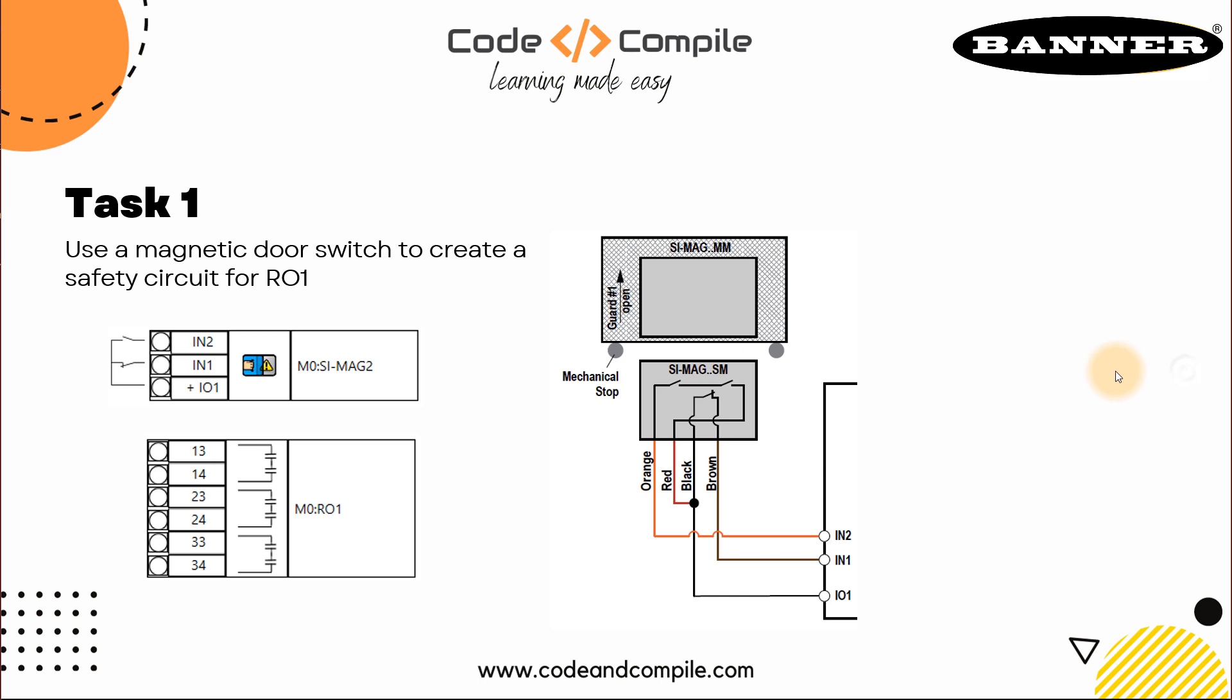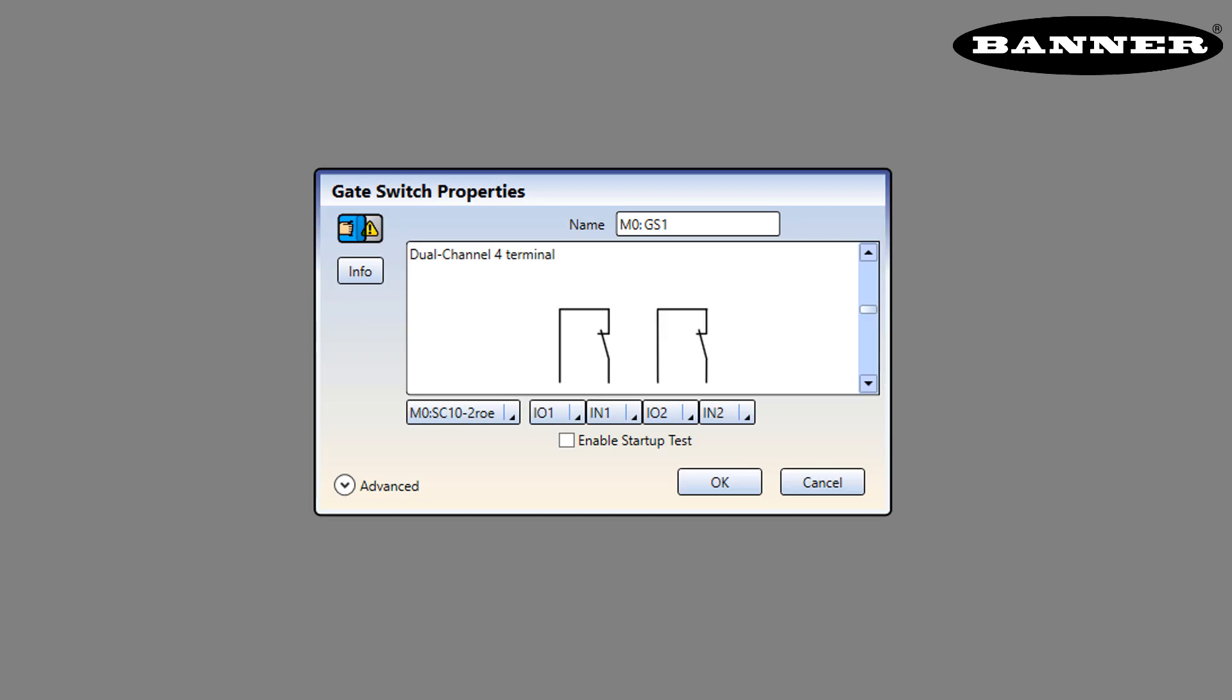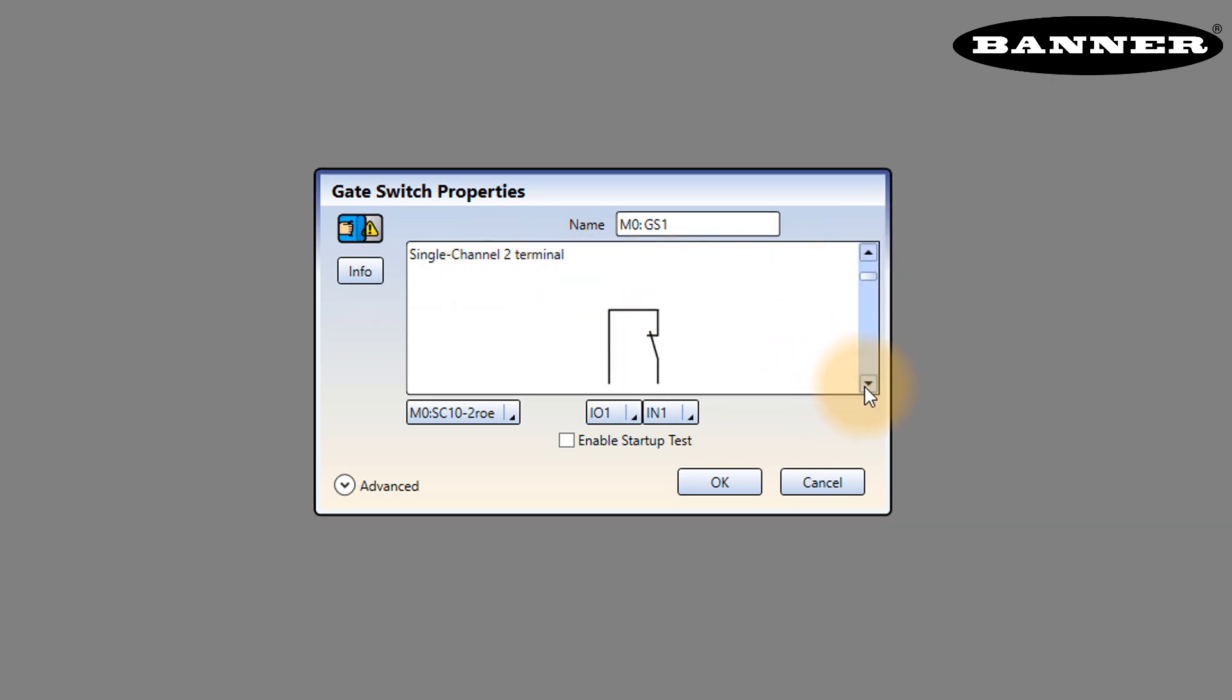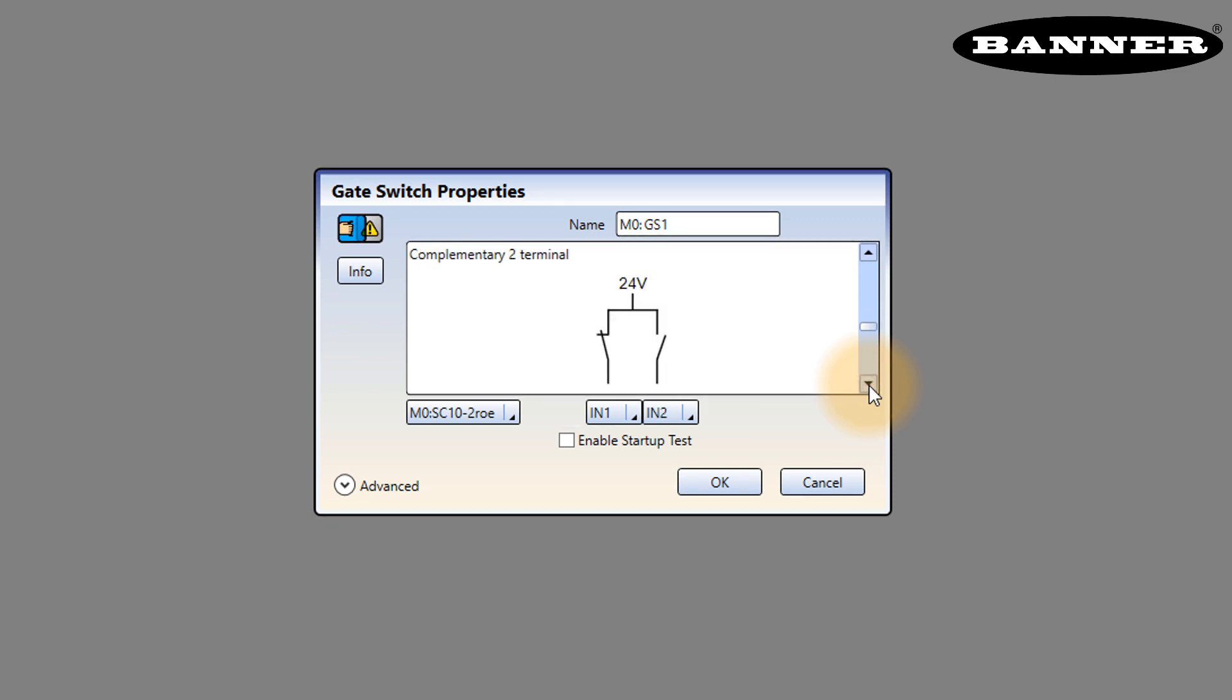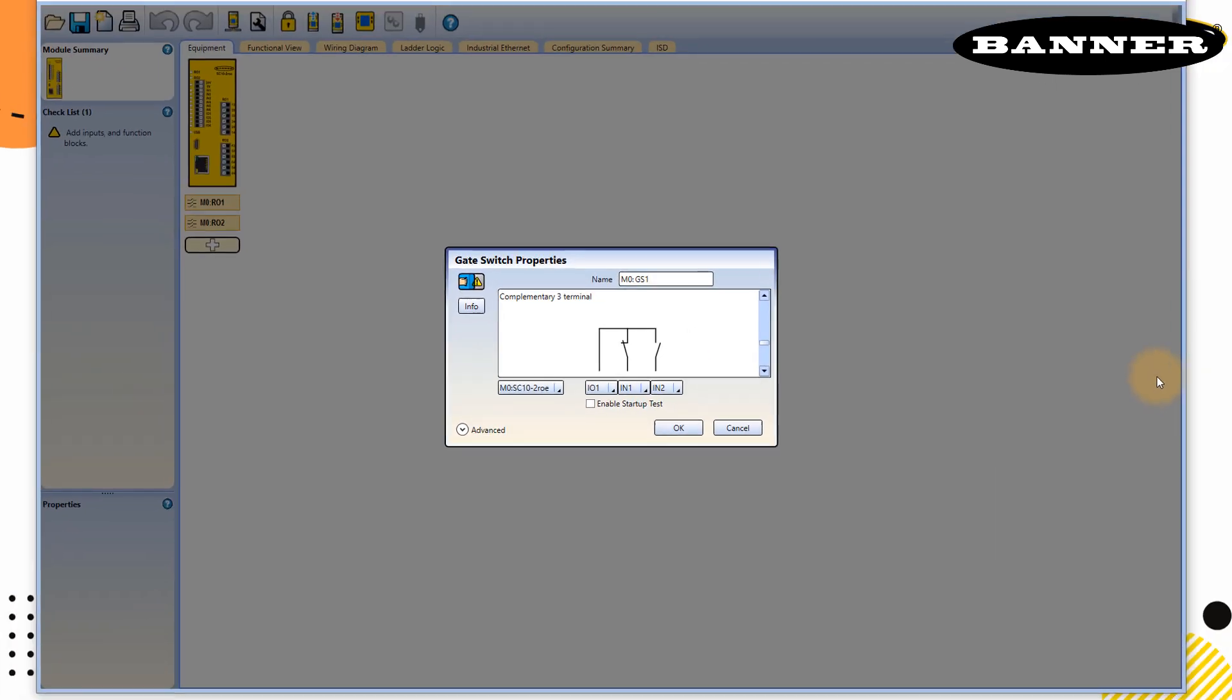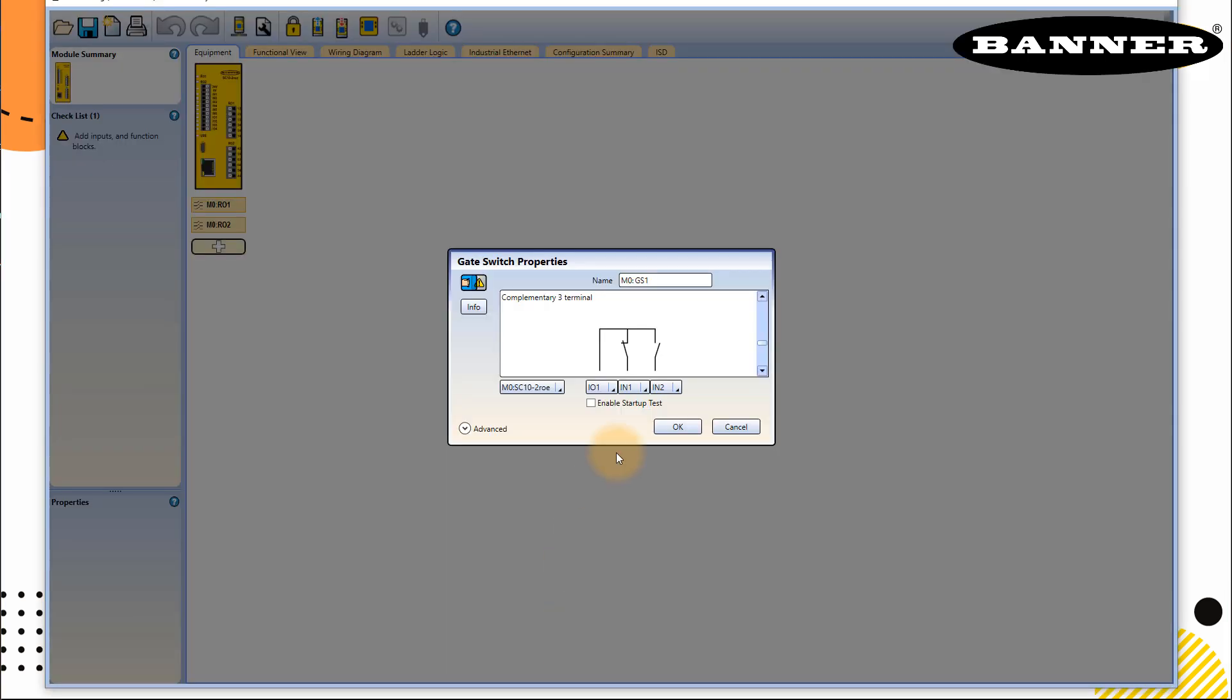So we click on this one, and then you will see different terminal configuration. And if you notice in our task, we have a configuration of three terminal complementary, if one is NO another is NC, this gives you extra security. So you can select this by navigating on the sidebar. So on the top, you have single terminal, and then you have single channel two terminals, and then single channel PNP. So if you come down, you will find complementary two terminals and in our case, it's three terminals. So this IO1 is already connected in my sensor. So if you see this diagram, we have connected this to IO1. And the signal from the sensor is connected to IN1 and IN2. So this is the perfect selection for us.